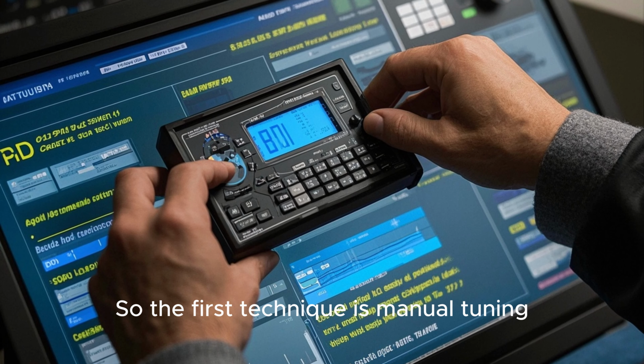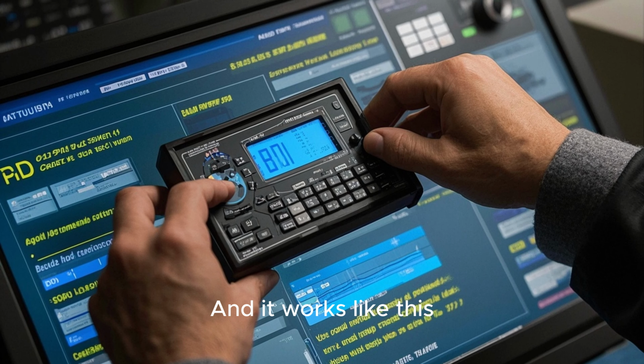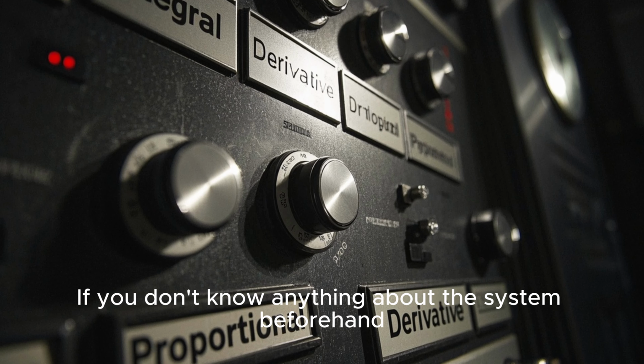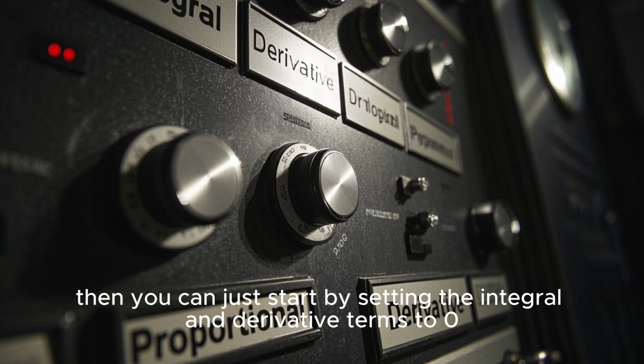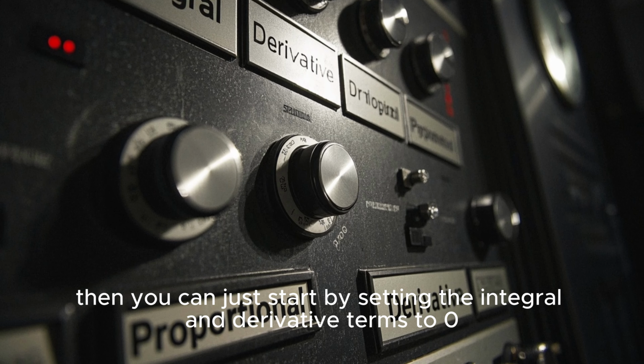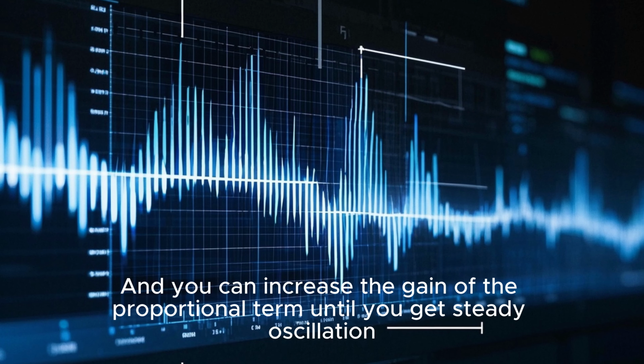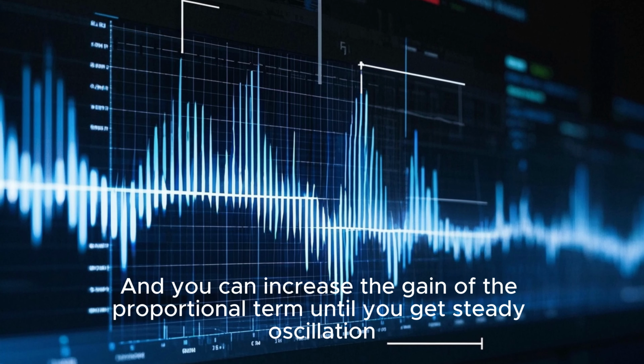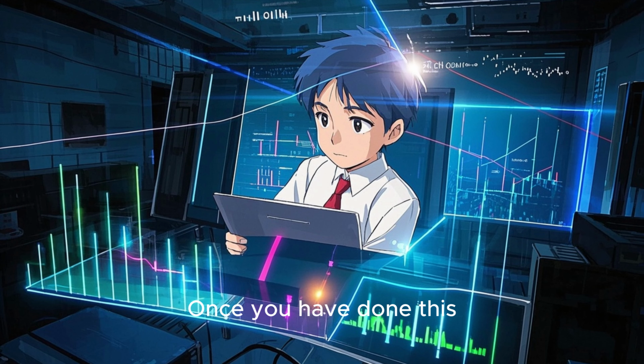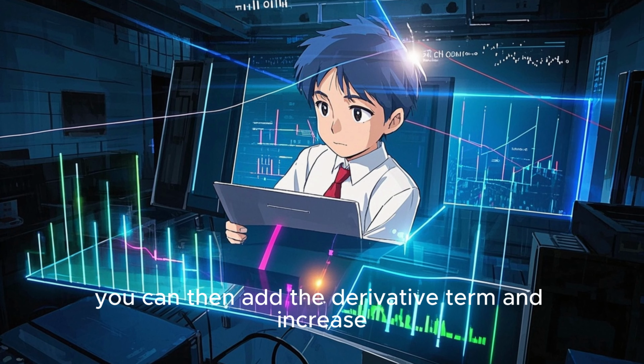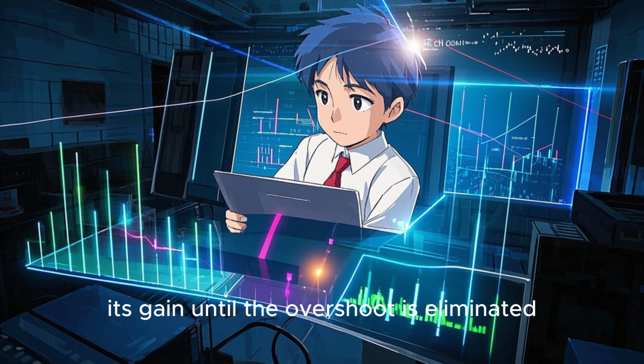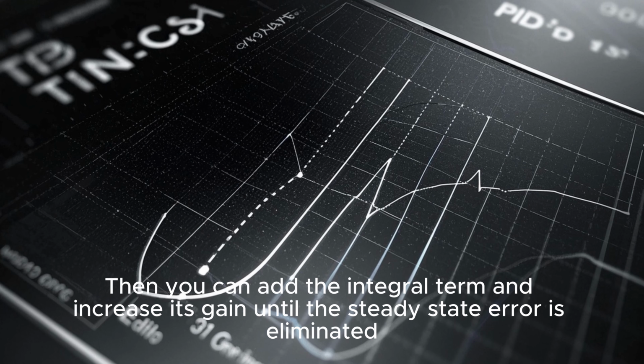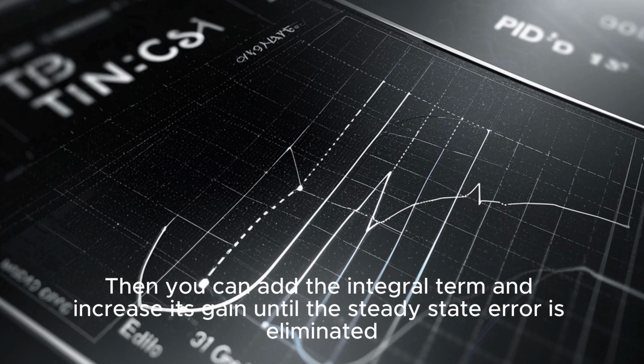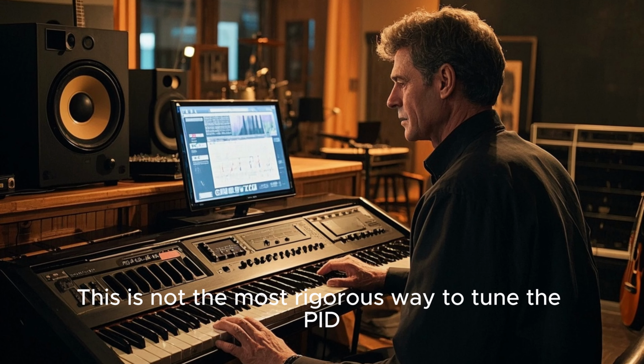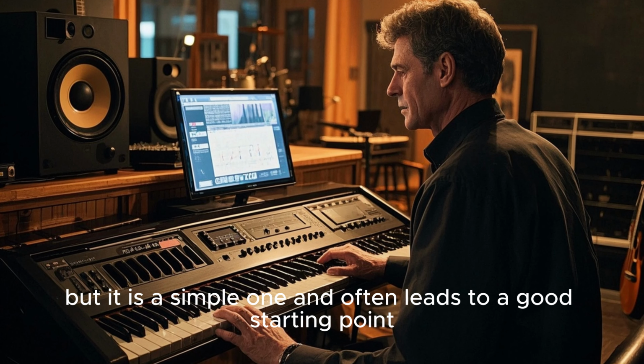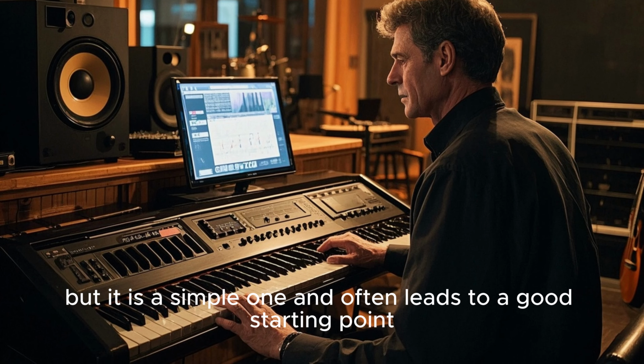So the first technique is manual tuning, and it works like this. If you don't know anything about the system beforehand, then you can just start by setting the integral and derivative terms to 0, and only use the proportional term. And you can increase the gain of the proportional term until you get steady oscillation. Once you have done this, you can then add the derivative term and increase its gain until the overshoot is eliminated. Then you can add the integral term and increase its gain until the steady state error is eliminated. This is not the most rigorous way to tune the PID, but it is a simple one and often leads to a good starting point.